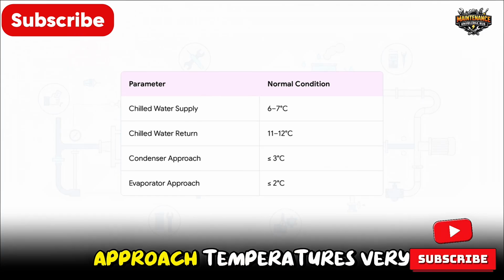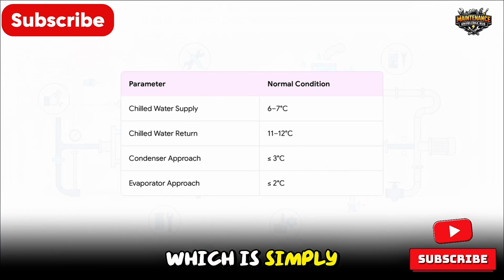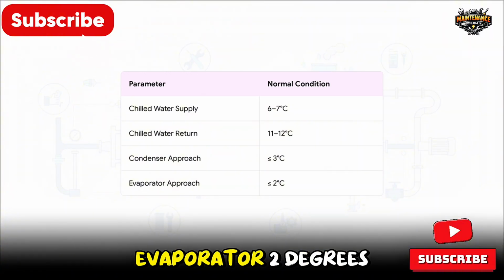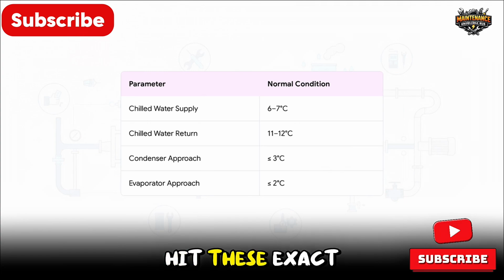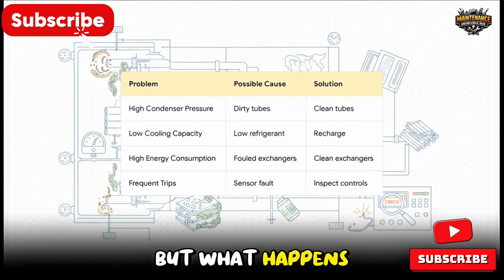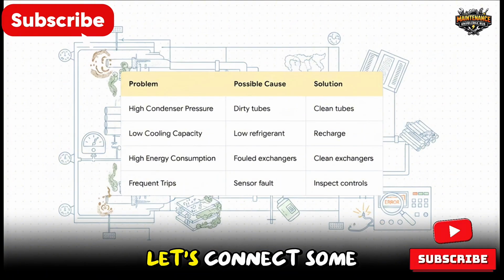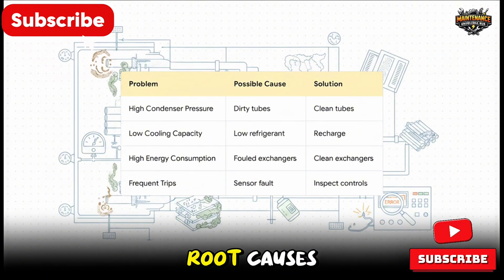We also watch approach temperatures very closely, which is simply the temperature gap between the refrigerant and the water. For the condenser, it should be 3 degrees Celsius or less, and for the evaporator, 2 degrees or less. Hit these exact numbers and you know your chiller is perfectly healthy. But what happens when things go wrong? Let's connect some common symptoms directly to their root causes.